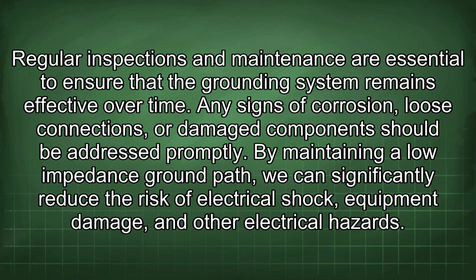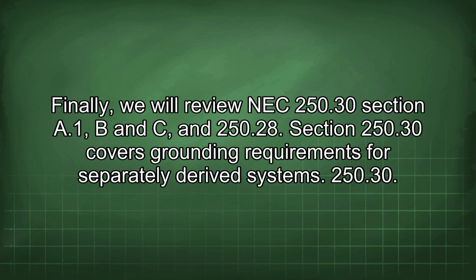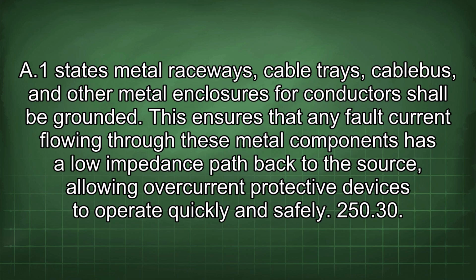Finally, we will review NEC 250.30 Section A1, B and C, and 250.28. Section 250.30 covers grounding requirements for separately derived systems. 250.30 A1 states metal raceways, cable trays, cable bus, and other metal enclosures for conductors shall be grounded. This ensures that any fault current flowing through these metal components has a lower impedance path back to the source, allowing overcurrent protective devices to operate quickly and safely.